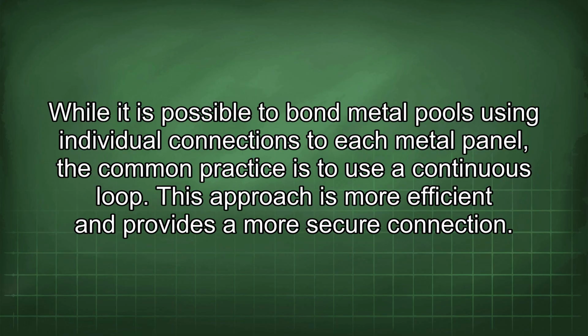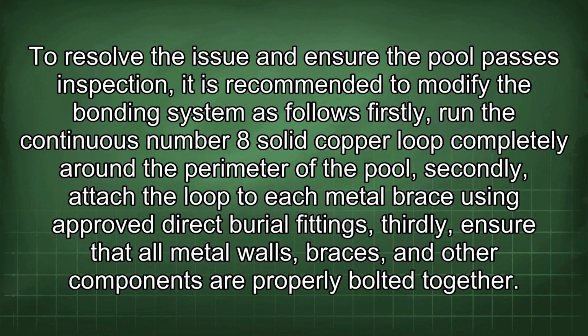While it is possible to bond metal pools using individual connections to each metal panel, the common practice is to use a continuous loop. This approach is more efficient and provides a more secure connection. To resolve the issue and ensure the pool passes inspection, it is recommended to modify the bonding system as follows.